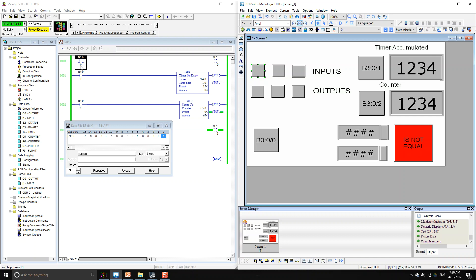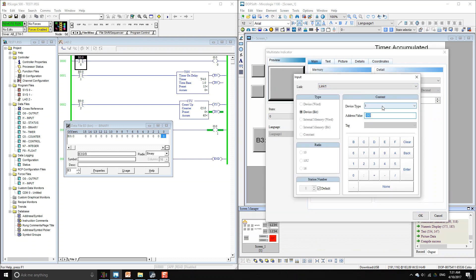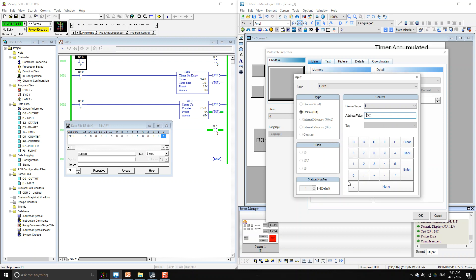For inputs you use the letter I, colon, zero dash zero. Then input word zero bit one, then bit two. You can also use the little wizard to enter the others — select device type Input, put in the address value, and remember to put the colon. If you don't, it will give you an error.